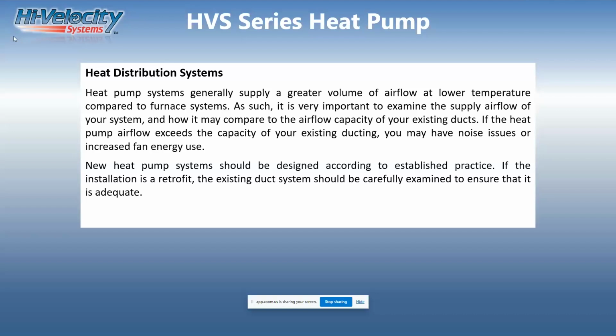I want to talk about heat distribution because that was one of the things I wanted to clear up here. I'm sorry, I don't know what happened there. Heat pump systems generally supply a greater volume of airflow at a lower temperature. So a heat pump's going to give you a lower temperature than a furnace. A furnace, that hot air is definitely warmer. So as such, it is very important to examine the supply airflow of your system, how it may compare to the airflow capacity of the existing ducts. If the heat pump airflow exceeds the capacity of the existing ducting, you may have noise or issues increasing the fan energy. Well, then your fan has to work harder. That's more energy that you're using.